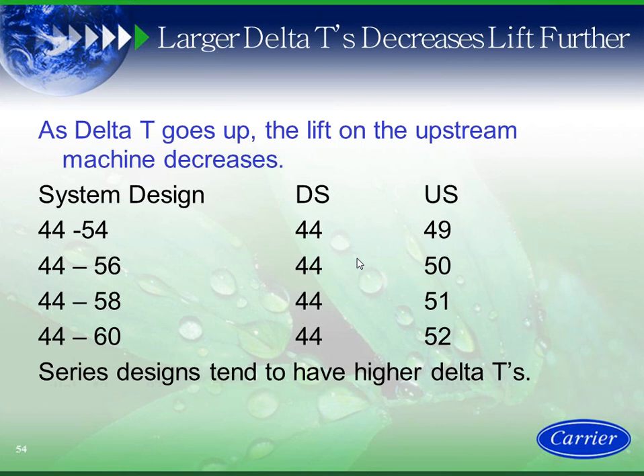Now, this is really cool. So now we start talking about increasing the delta T on a coil. Now, you can't just say I want a chiller plant with a high delta T. I have to have coils and air handlers that can deliver the high delta T, because one of the biggest issues on a chiller plant is low delta T syndrome. So in this case, if I can actually get and maintain a constant delta T, my series counterflow chiller plant actually gets more efficient as the upstream temperature goes up. So as I increase the delta T on the chiller plant, my upstream delta T goes up. Therefore, I'm actually saving energy by going to a higher delta T.